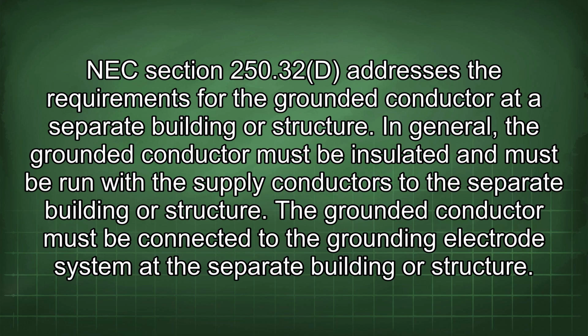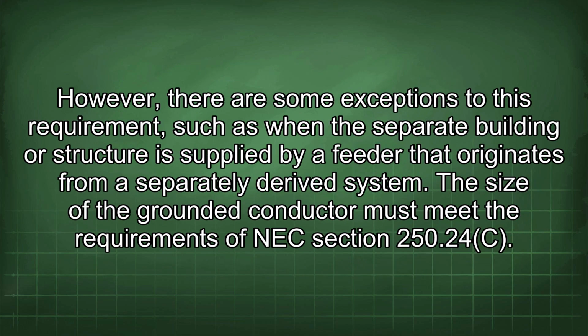NEC Section 250.32d addresses the requirements for the grounded conductor at a separate building or structure. In general, the grounded conductor must be insulated and must be run with the supply conductors to the separate building or structure. The grounded conductor must be connected to the grounding electrode system at the separate building or structure. However, there are some exceptions to this requirement, such as when the separate building or structure is supplied by a feeder that originates from a separately derived system. The size of the grounded conductor must meet the requirements of NEC Section 250.24c.